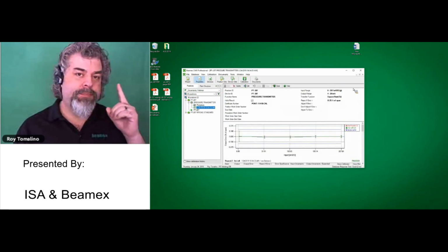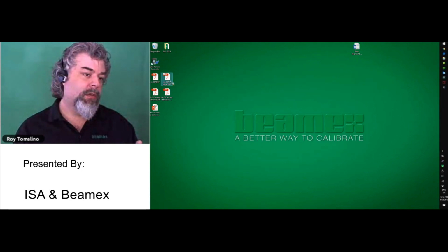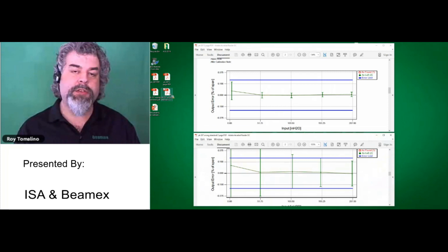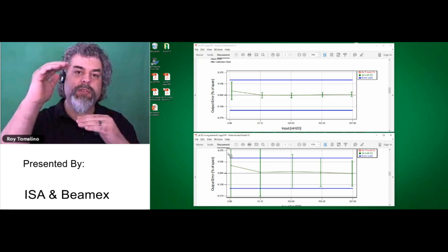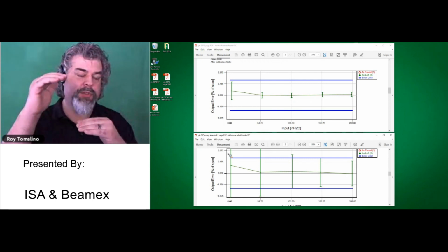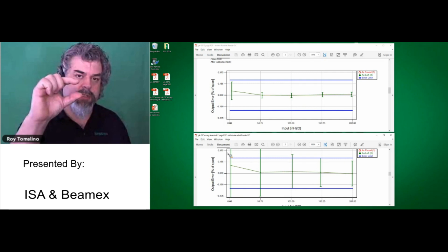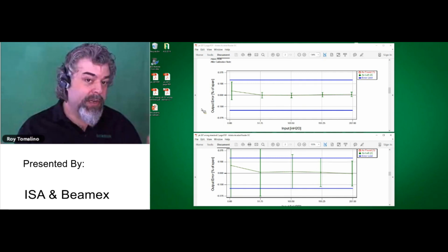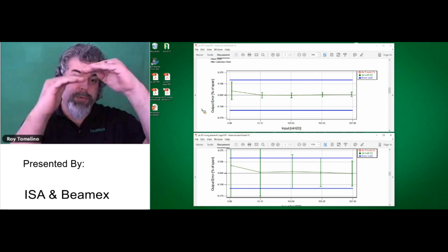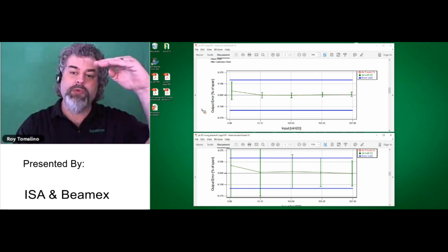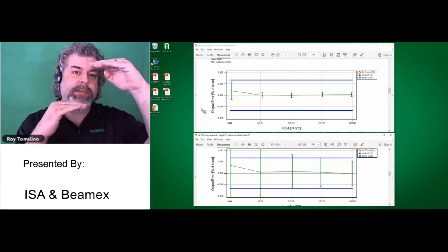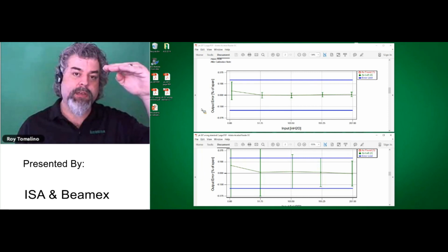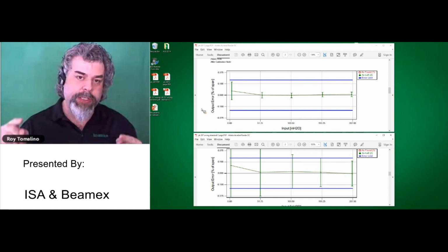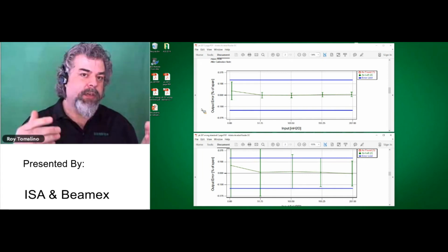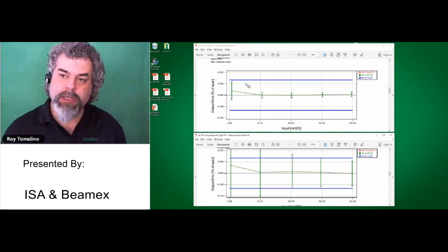But let me do this. These are the graphs. The bottom one is the first one that I did with those uncertainty guard bands that are just monstrous. They're huge, and that's using the 300 PSI module to calibrate something that's 207 inches. The top one is using a 30 PSI module, and we can see that with the uncertainty, every single one of those we can be confident to a 95% confidence level that everything is passing. And visually, this is what uncertainty looks like. Again, this is a representation of uncertainty.